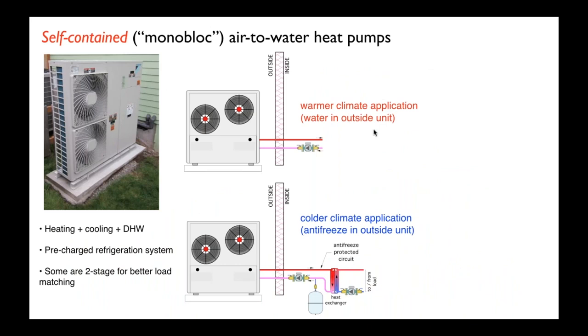There are a couple different hardware configurations for air-to-water heat pumps. What is known as a monobloc, and actually that's how they do spell that in Europe, no K. I like to use the term self-contained. All the parts and pieces necessary for the heat pump, including the refrigerant, are put together at a factory. The refrigerant is added. You buy it with the refrigerant already in. So essentially, you're making water or a solution of water and antifreeze, you're making those hydronic connections to the outdoor unit. You're extending the hydronic system outside, connecting it to the unit.